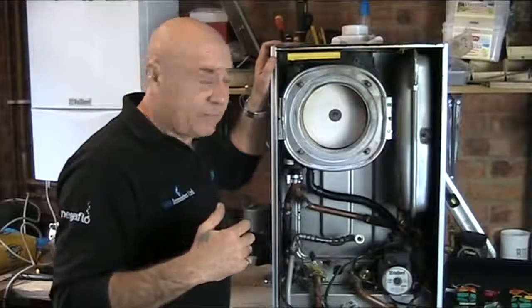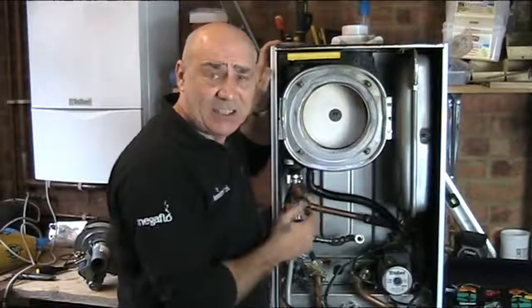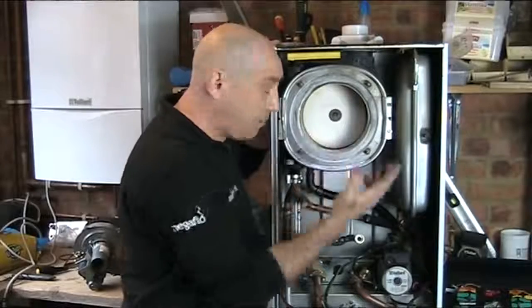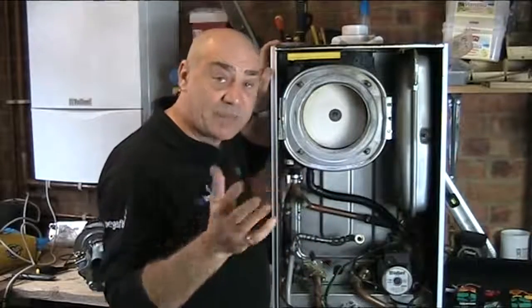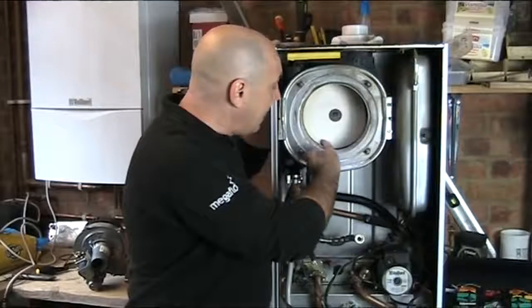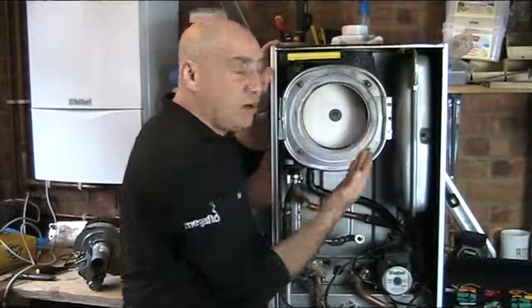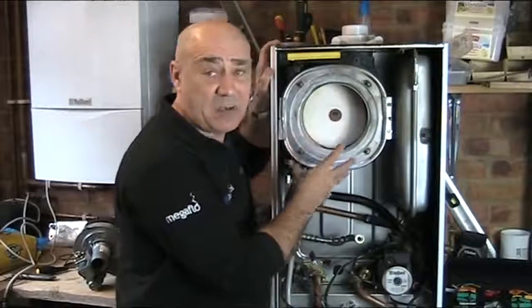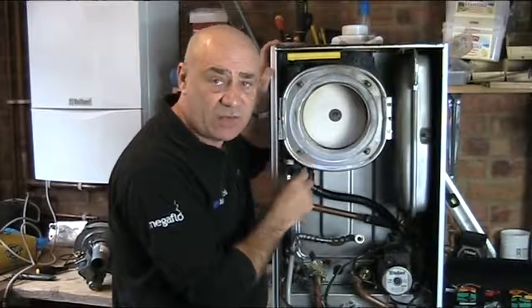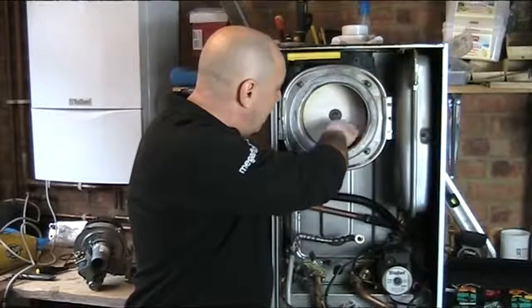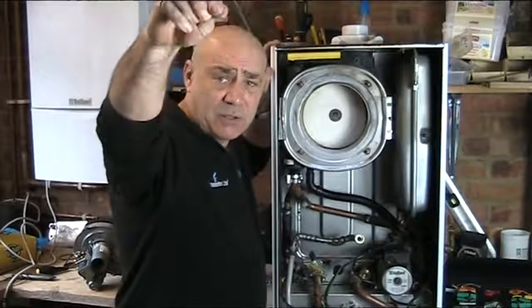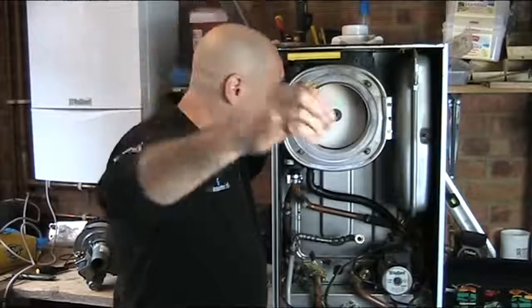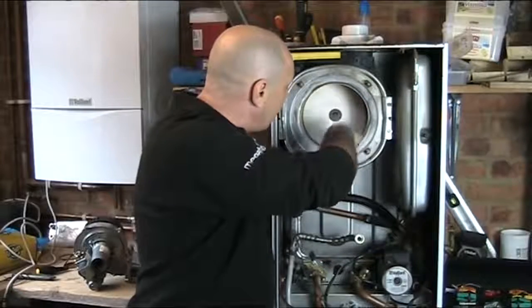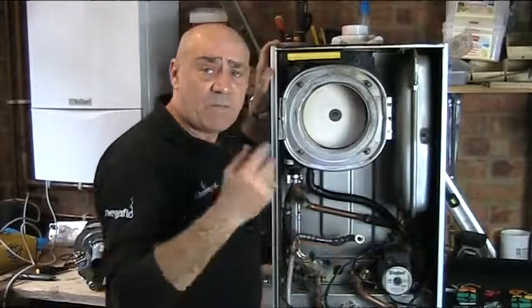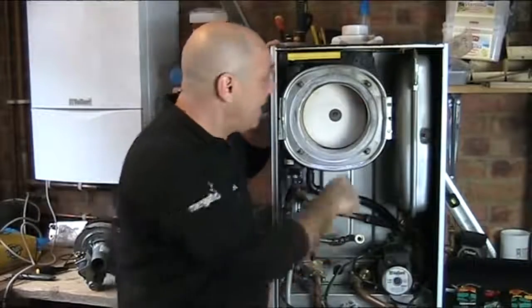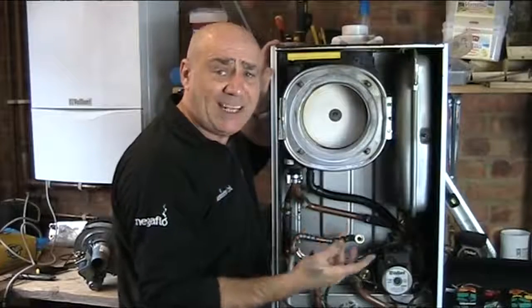Once we've got the burner out, we can see then and inspect inside the heat exchanger. Now this you can see, well you may not be able to see actually because obviously there's a bit of distance here, but if you look in here, this is absolutely rotten, and that's because this boiler had never been serviced. And I can pick out, you might be able to, if I sprinkle that down there, this is blocked solid with sediment and oxides from the combustion process. Again, this has never been inspected or checked or cleaned.